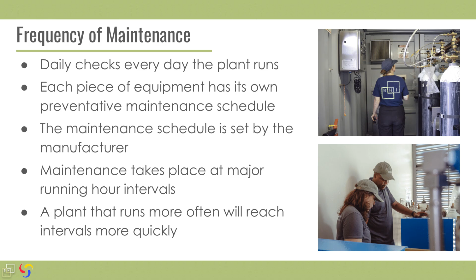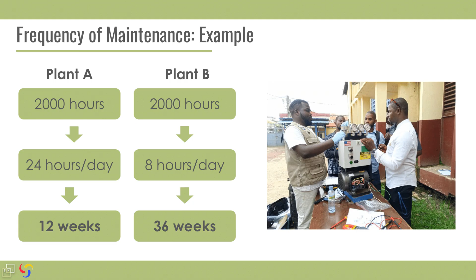Let's explore a quick example of how plant running hours impact the frequency of service intervals, looking at how quickly two plants will reach 2,000 hours. Plant A runs 24 hours per day, while Plant B runs 8 hours per day. Plant A will reach 2,000 hours in 12 weeks, while Plant B will reach 2,000 hours in 36 weeks. This is why it is important to track maintenance in hours and not weeks or months.